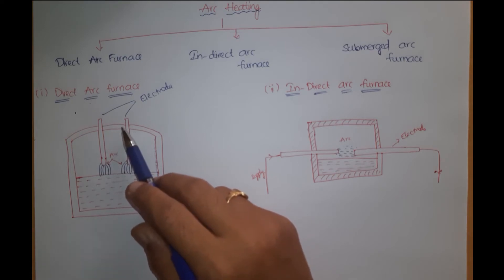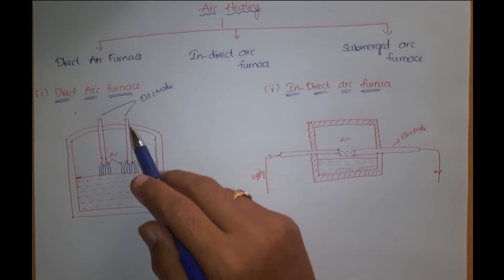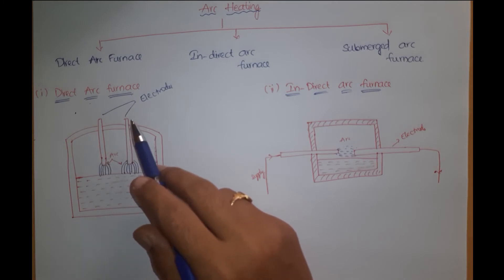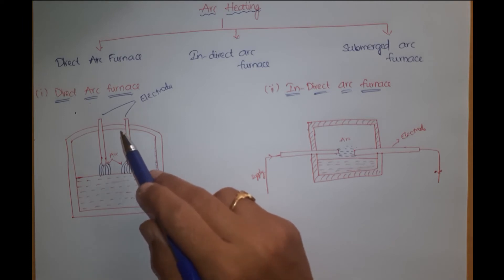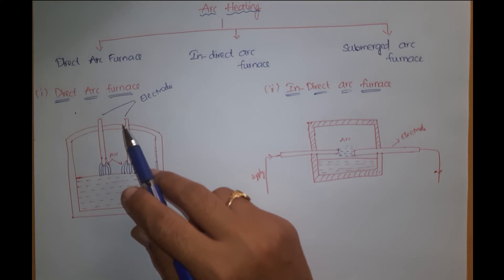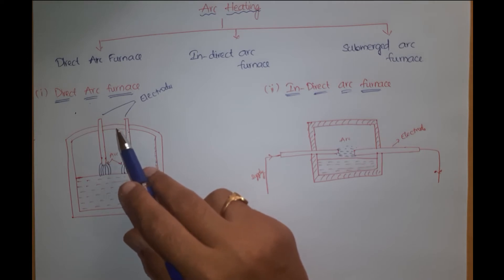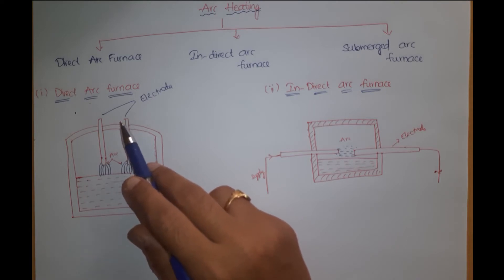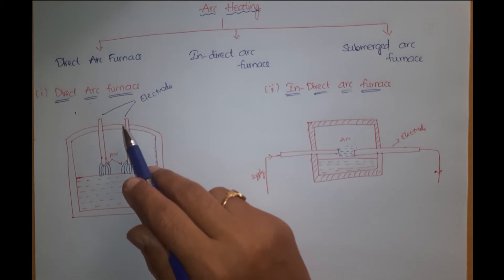The furnace consists of chambers to insert the electrodes, which may be constructed with either graphite or amorphous carbon. The conductivity of graphite is double that of carbon, and it can carry two and a half times the current that can be carried by carbon. Although graphite is costlier, graphite electrodes are usually employed because the diameter of a graphite electrode required is only about two-thirds that of a carbon electrode to produce the same amount of heat.